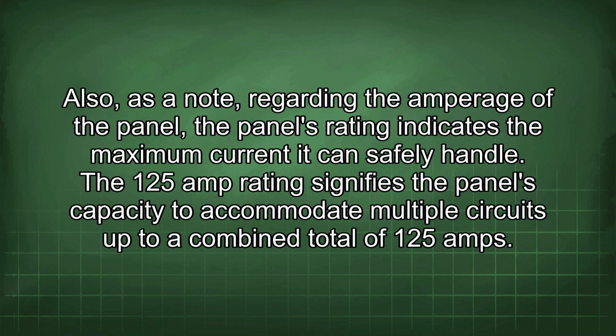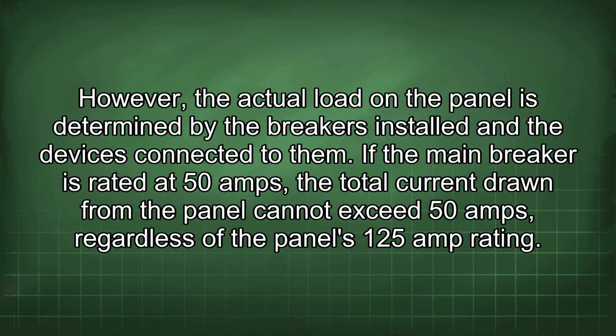Also, as a note, the amperage rating of the panel indicates the maximum current it can safely handle. The 125 amp rating signifies the panel's capacity to accommodate multiple circuits up to a combined total of 125 amps. However, the actual load on the panel is determined by the breakers installed and the devices connected to them. If the main breaker is rated at 50 amps, the total current drawn from the panel cannot exceed 50 amps, regardless of the panel's 125 amp rating.